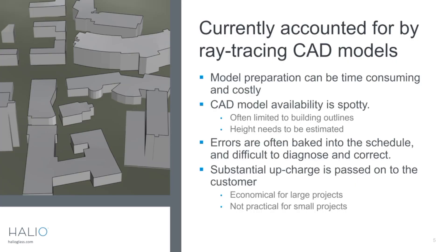Currently, most automated shading control systems can account for exterior geometry. What they do is build a CAD model of the building and the site, and then ray trace from the windows to the site. The trouble with this is that setting up the CAD model and verifying that it's accurate can cost money and add a lot of time to the project.